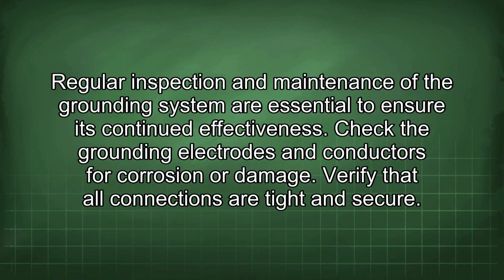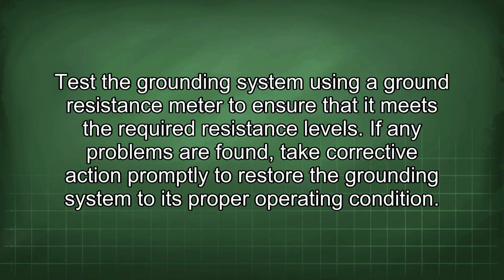Regular inspection and maintenance of the grounding system are essential to ensure its continued effectiveness. Check the grounding electrodes and conductors for corrosion or damage. Verify that all connections are tight and secure. Test the grounding system using a ground resistance meter to ensure that it meets the required resistance levels. If any problems are found, take corrective action promptly to restore the grounding system to its proper operating condition.